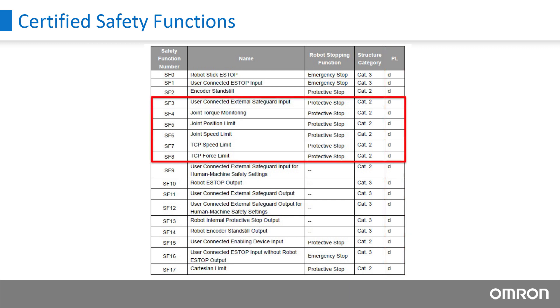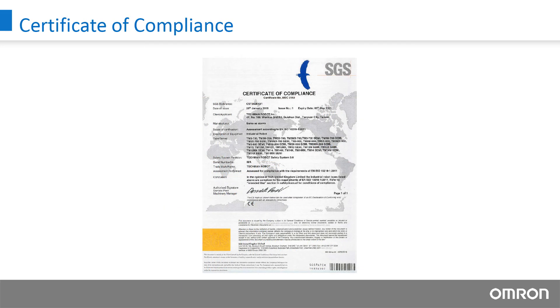Force and speed monitoring are the defining capabilities of collaborative robots. The safety functions of the OMRON TM robots, including Power Limit and Force Limit, are always active and compliant with ISO 13849-1. All compliance with safety standards were tested and certified by SGS, an organization based in Switzerland that provides inspection, verification, testing, and certification services. The certificates of compliance from SGS can be found in our safety manual.